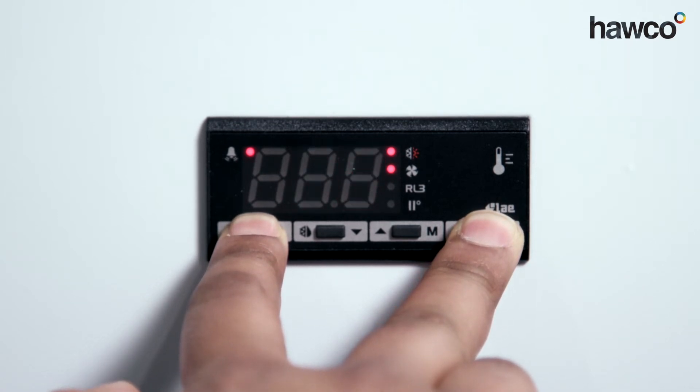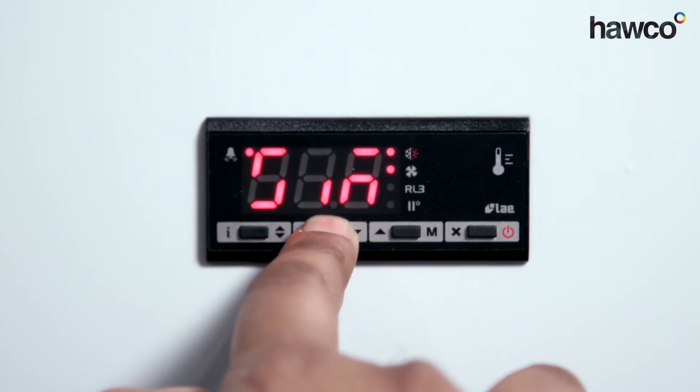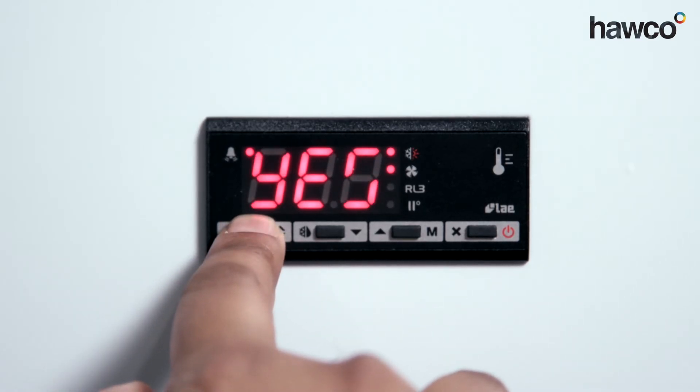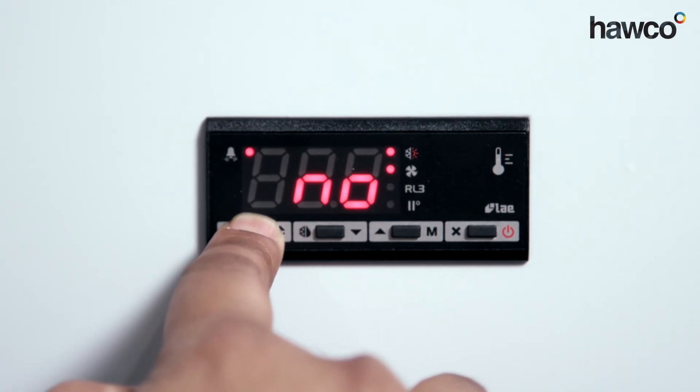So by holding two end buttons together, we enter the parameters. We scroll through till we find T2, push and hold the I button. You can see it says yes. We want it to say no, the second probe is not needed.